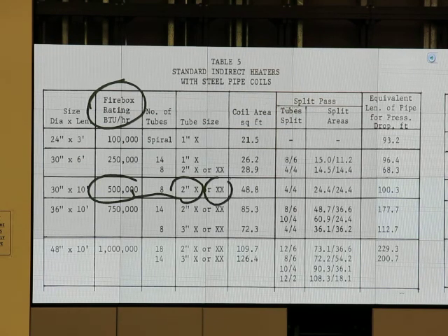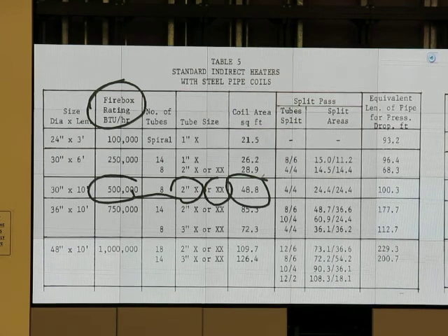When I get the U value, then I can do A equal to Q over U and T sub M. Then I can tell what the required coil area is. And if the provided coil area is larger, then we're good. Then we are almost done. The reason I say almost is that we have not checked the erosional velocity.